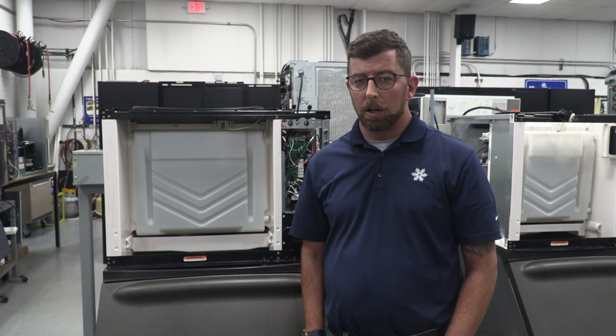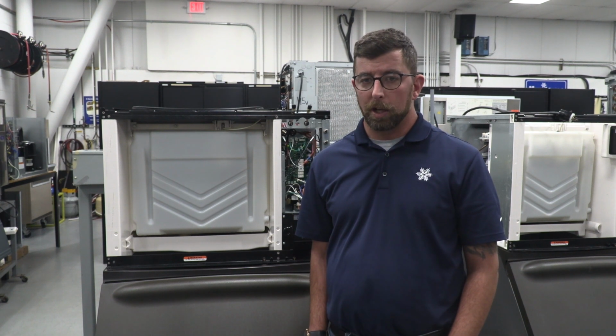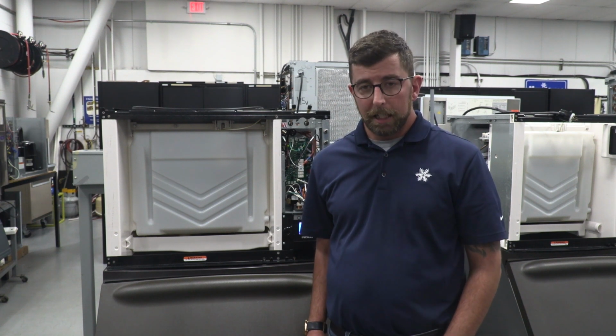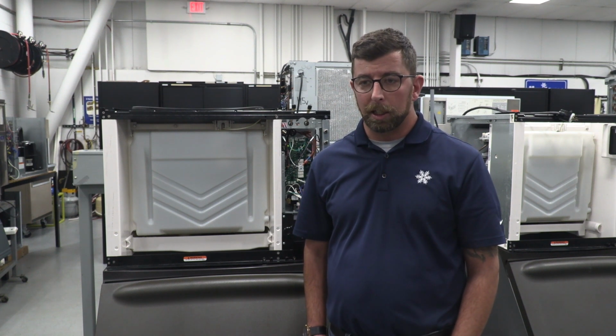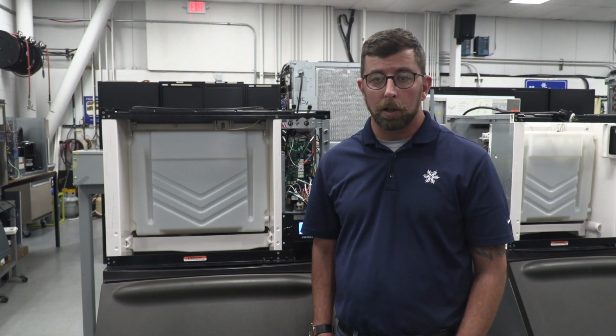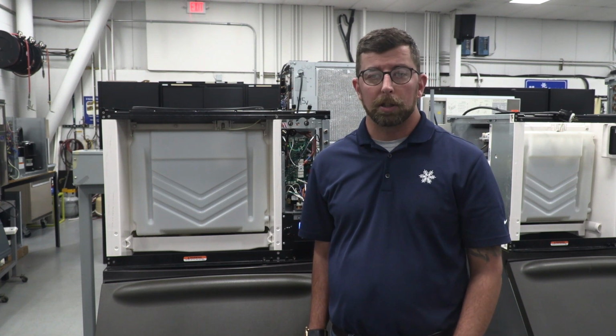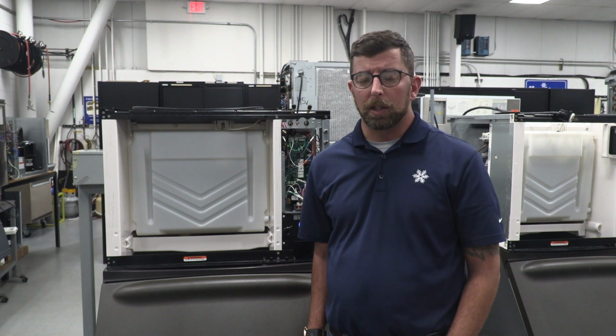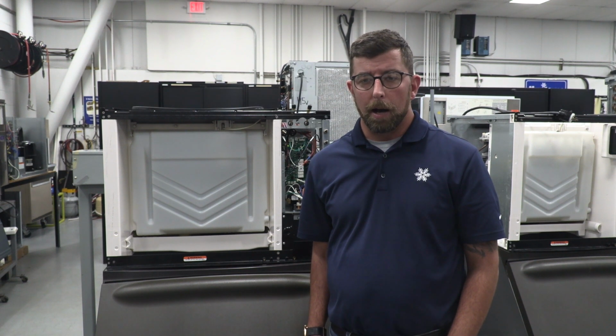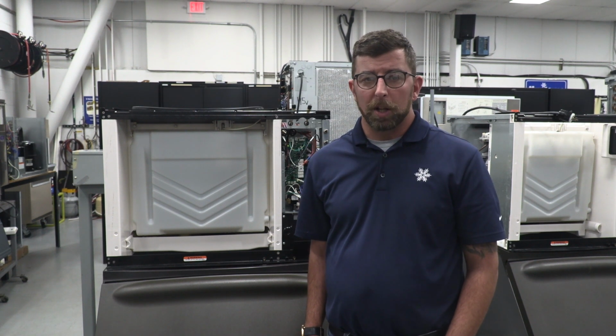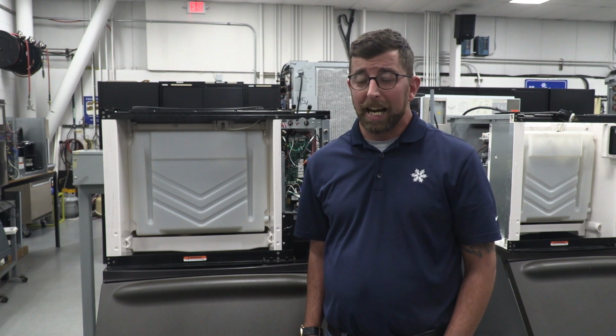This is a small water valve. It feeds at less than a half a gallon a minute. It should not take away all your pressure. But if you have verified, yes, I have water pressure coming to this ice machine, I have either replaced the water filter, I've taken the back line off and verified, yes, water comes through, now you know that your problem's with the water inlet valve itself. Either you've got something plugging up the screen in there or the valve just mechanically can't open.